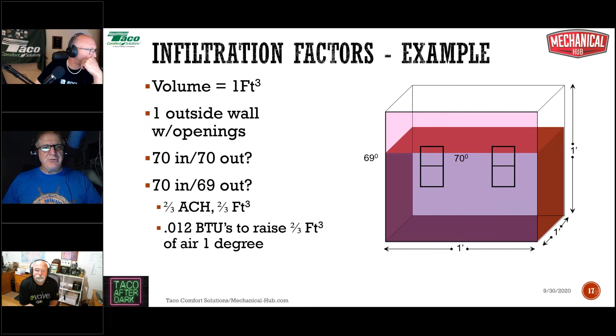Now, what would happen if it turned out to be 69 degrees outdoors? Now, technically, we do have heat loss. What's happening here is 2/3 of the air in that room, in this case 2/3 of a cubic foot of 70-degree air, is leaking from inside to outside, and it's being replaced by the same amount of 69-degree air. What 0.012 represents is the number of BTUs needed to raise 2/3 of a cubic foot of air 1 degree Fahrenheit in 1 hour. So that's where that factor comes from.